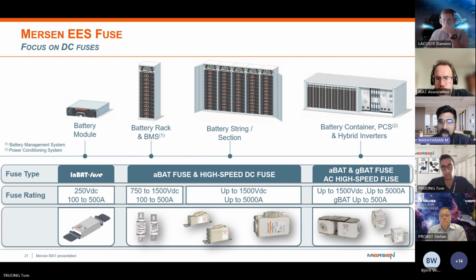It's possible. And when we talk about the PCS or the battery container level fuses, we could have an ABAT and a GBAT fuse. The ABAT is a semiconductor-type battery fuse which has a partial range of protection, employed for short circuit conditions, and GBAT is more pronounced for short circuit and overload conditions. So this is the key defining factor between ABAT and GBAT fuses, and the right fuse has to be selected depending on the circuit topology.